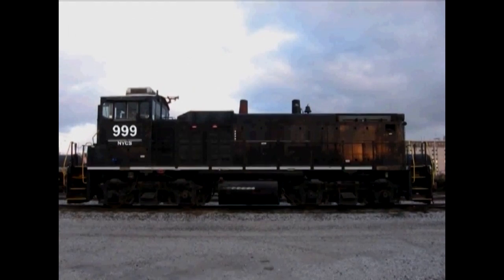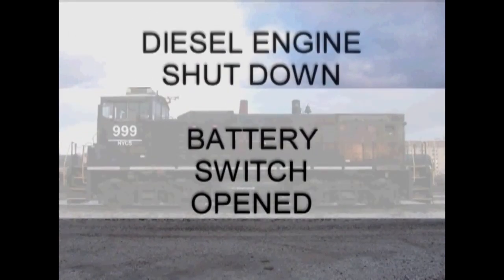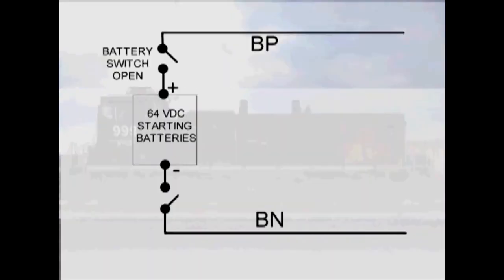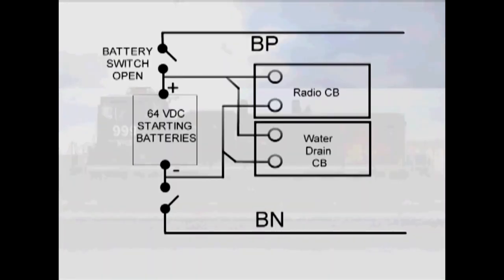The electrician had shut the diesel engine down and opened the battery switch, and thought that this was sufficient protection to allow him to work on the system safely. Normally, the high current draw caused by the ring shorting the circuit would cause the circuit breaker to open. Because the circuit was hooked directly to the 64 VDC starting batteries, no circuit breaker tripped. This particular locomotive had several circuits, the cab radio and water drains, wired directly to the batteries.